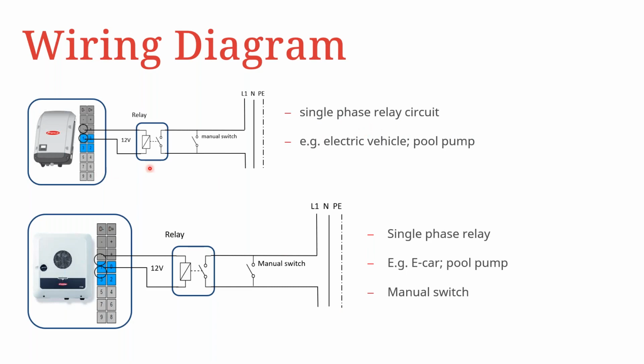So you can see here, you are connecting from any of the IOs. We have, for instance, a connection from IO1 and a negative connection that is used to activate an external relay. This relay then would connect any of these loads, whether it's an electric vehicle, a pool pump, or even a heater. And whenever there is excess energy available, the inverter through the IO allows the relay to close. Once this closes, this particular load is able to utilize whatever excess energy is available from the inverter.